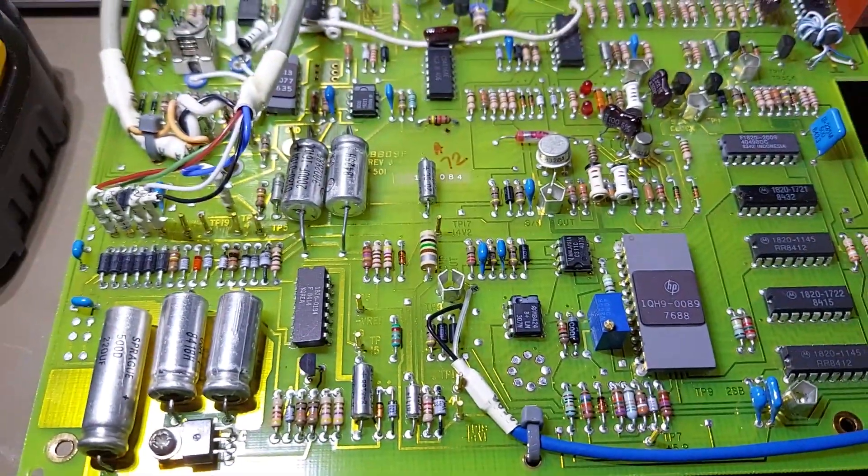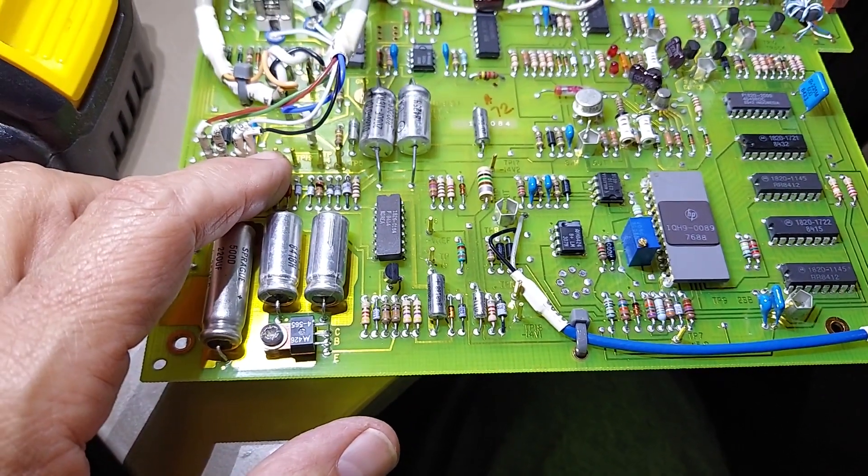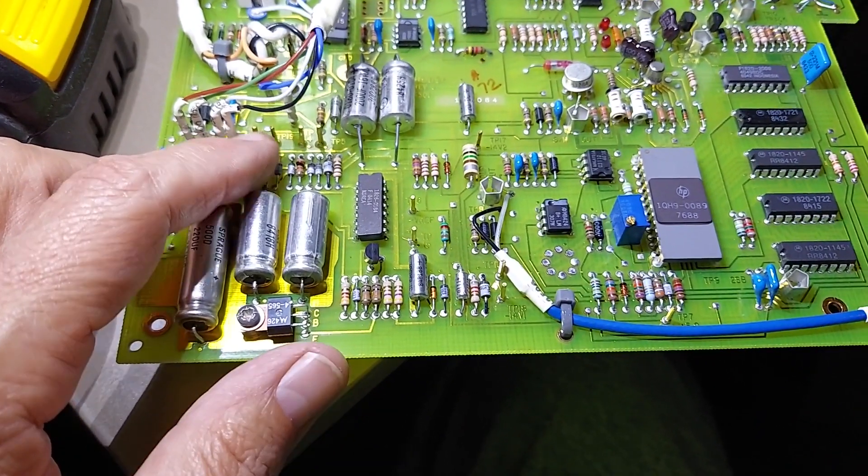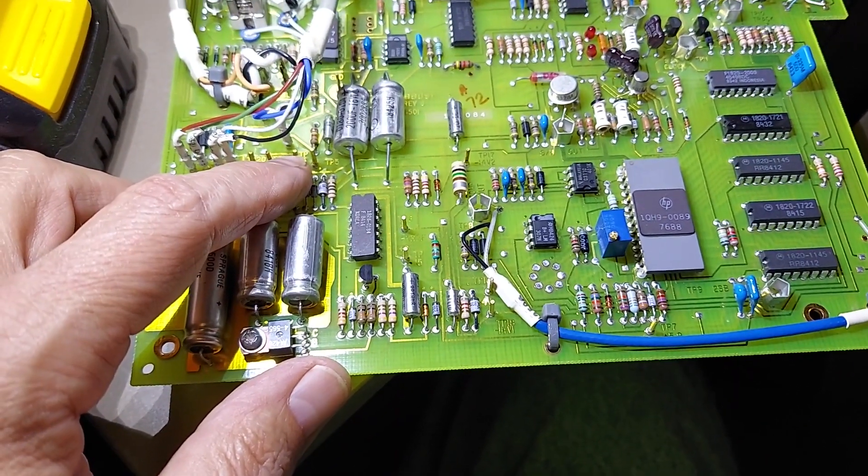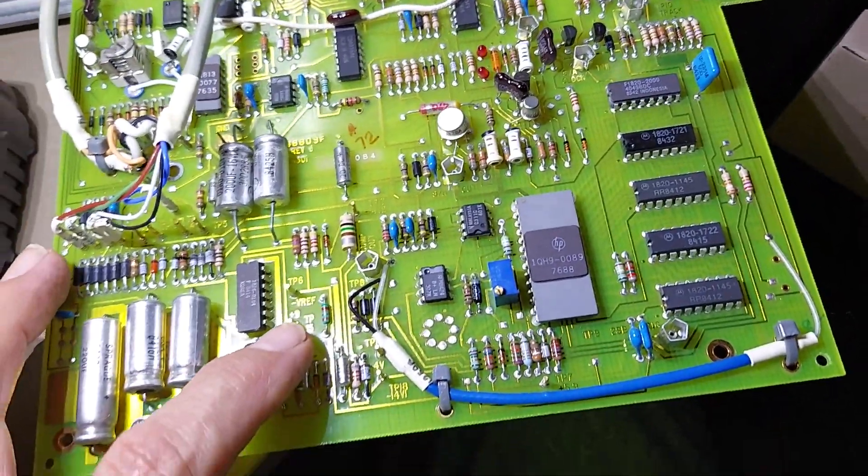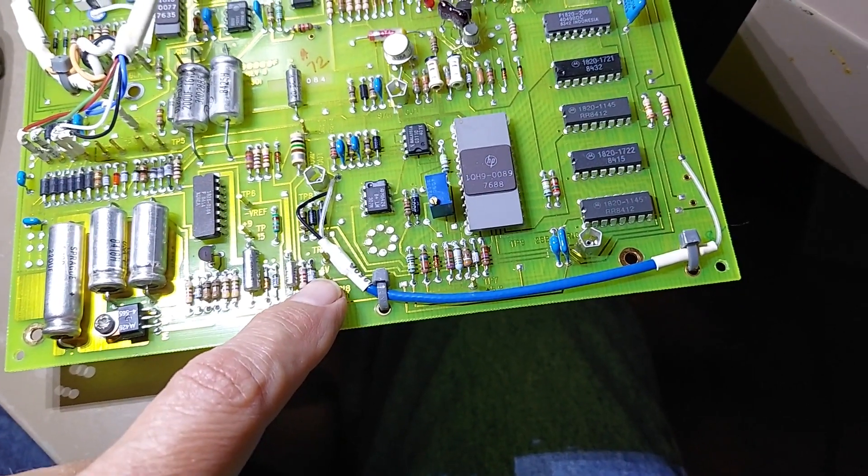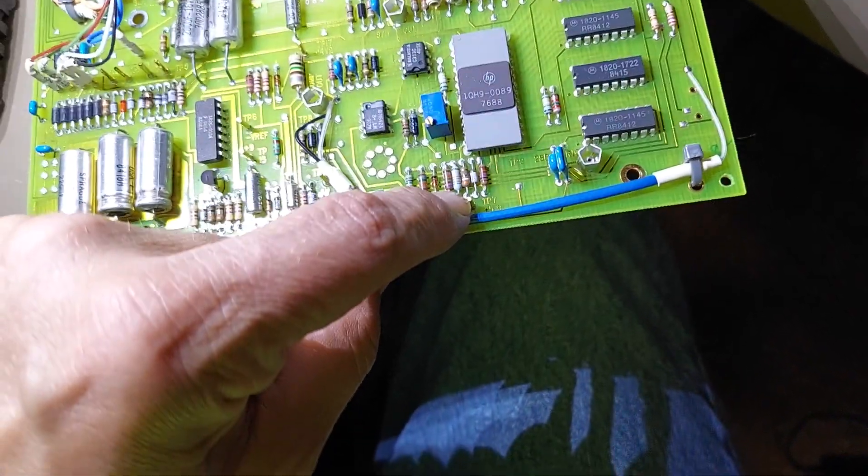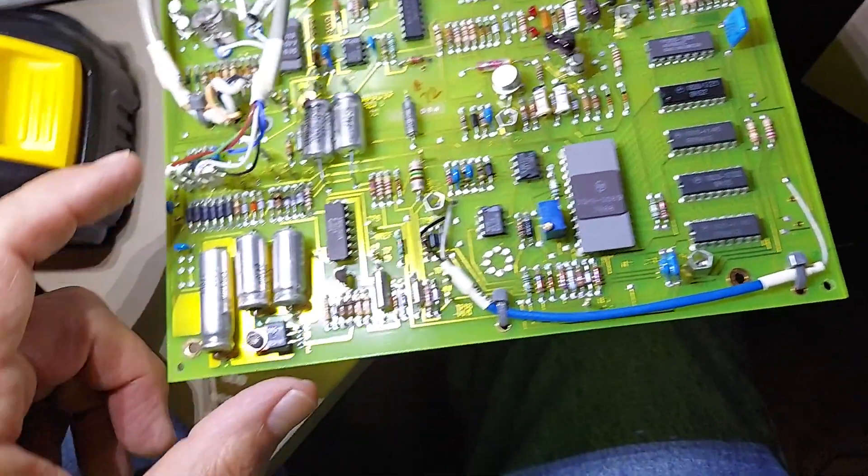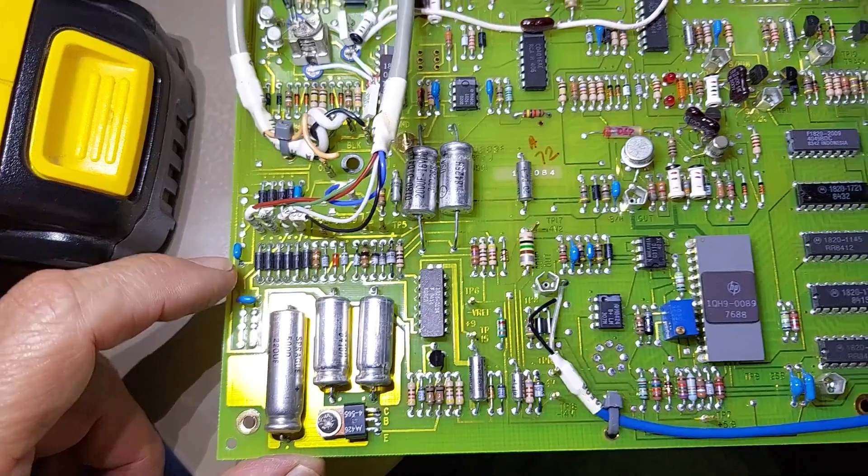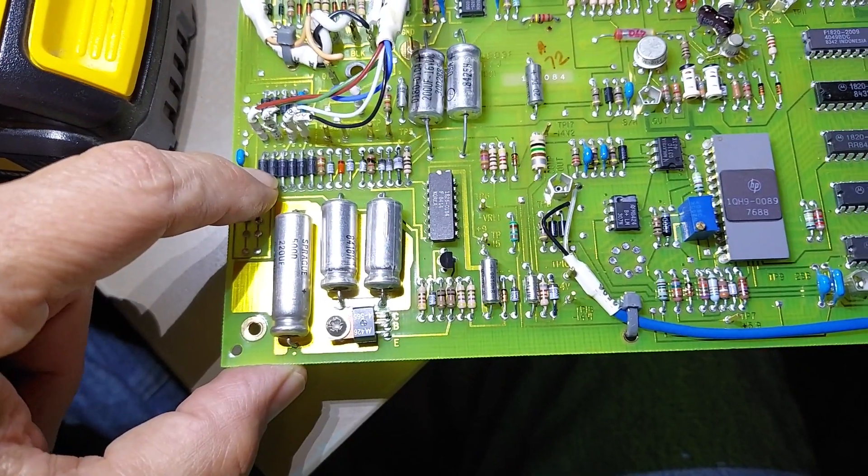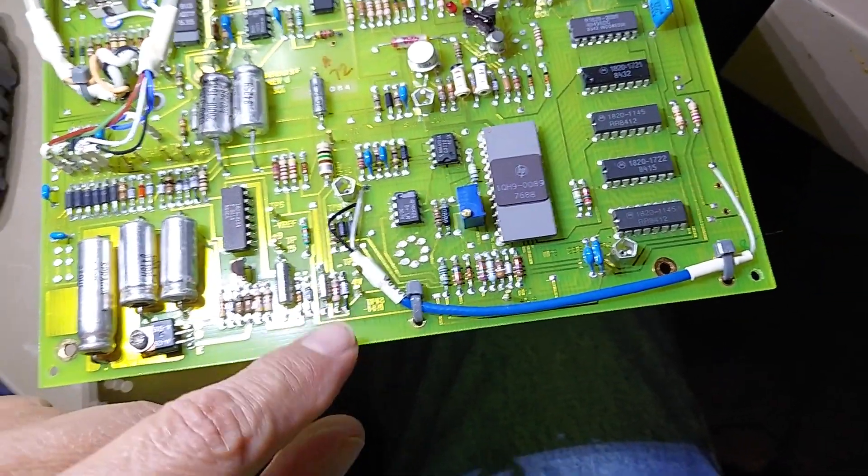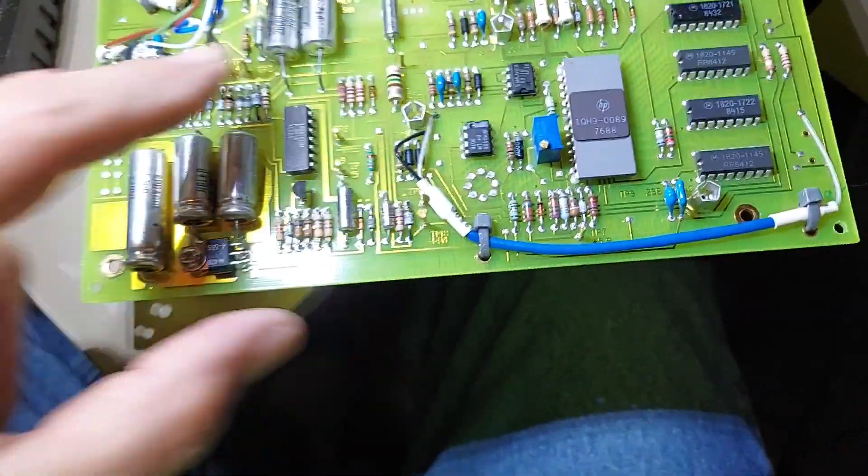Well, after a little bit of testing here, I tested some voltage rails. Here there's supposed to be minus 25 volts. Well, there's only minus 6. Here, there's supposed to be minus 20, and there's about a minus 7. It's supposed to be a minus 2 here, and there's a minus 2. There's a plus 2, which is supposed to be a 2. The 9 volt reference here is fine. The 14 volt reference on the other end, that's only 7 volts. This 5.9 volt here is fine. So, I've tested all these diodes, and they all seem to test okay. And here is where a voltage doubler is. And these two diodes here generate the negative 20 some odd volts or 25 volts this thing needs.